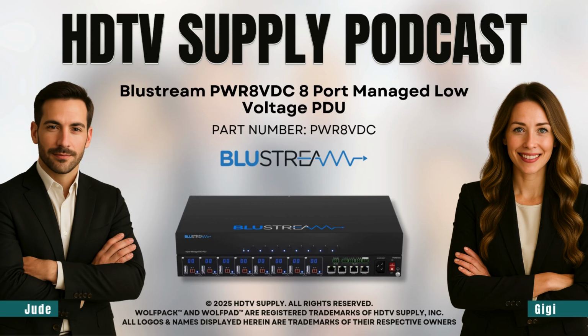But it's not just the Phoenix ports, there are also managed USB-A ports, a clever addition. 8 managed USB-A ports power other third-party devices in the rack, but you have to watch current limits. Ports 1 to 4 give you 5V at 1 amp, while ports 5 through 8 are limited to 500 milliamps, so there's precise power budgeting. It also has the expected safeguards: overload protection and interference filtering, since reliability is everything in these setups.